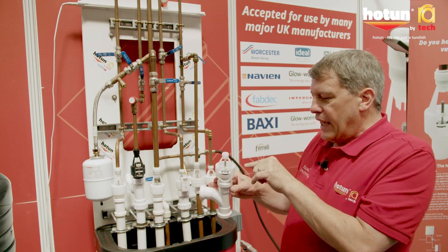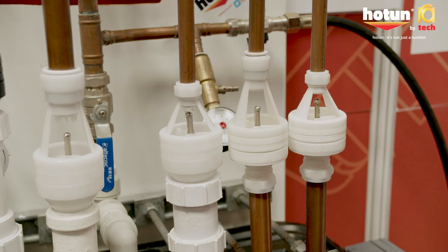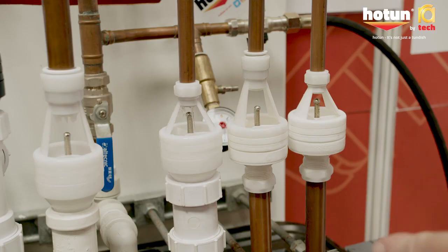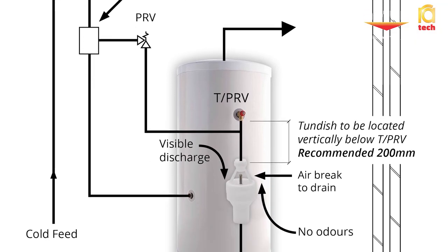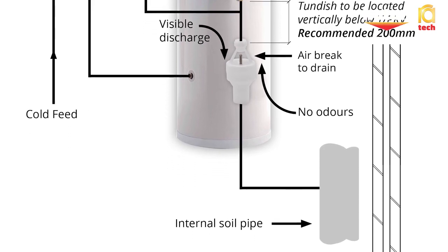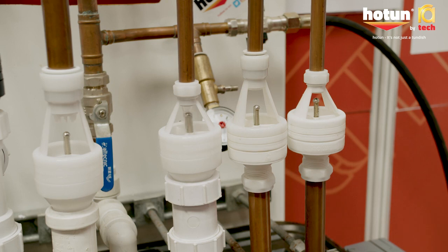Unique to Hotun is the open-sided construction. When the water puddles in the top of the Tundish, the installer can see that water and can actually touch and feel it — that's totally unique to this design. With a temperature relief valve, because that discharges high volumes, the valve has got to open sufficiently to allow that high volume flow of water through, so it's got to deal with drips and high volume flows, which this design does.